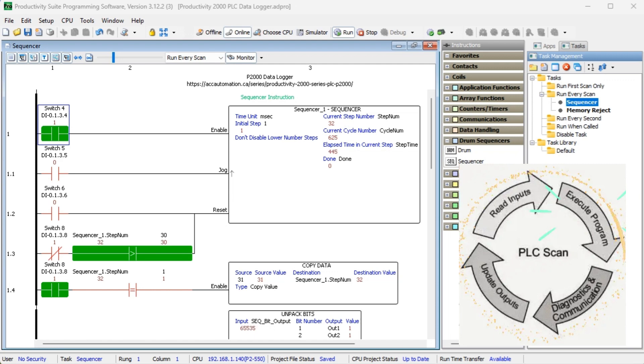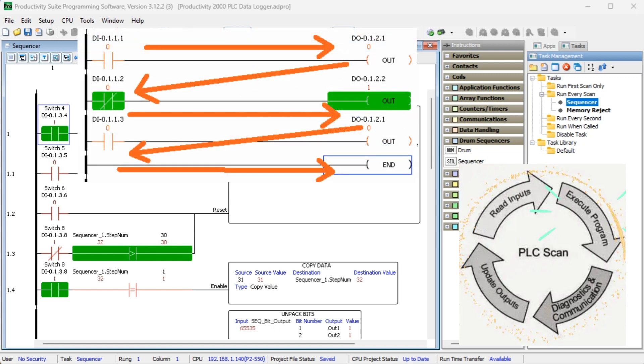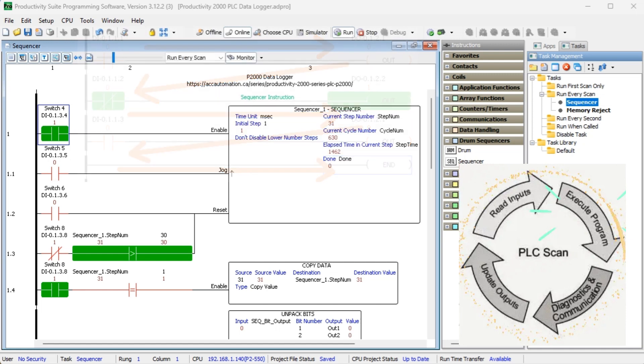There are four essential parts of the PLC scan cycle: read inputs, execute logic or your program, diagnostics and communication, and update outputs. Since outputs are generally set only once per scan, the last ladder logic scan will be the one that sets an output if the logic is duplicated.